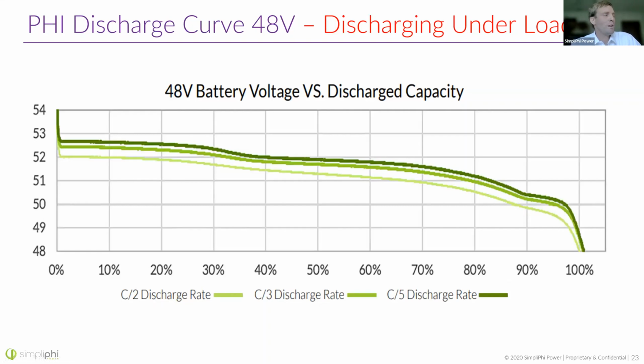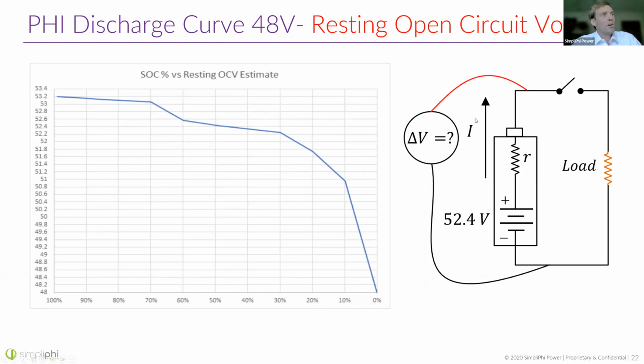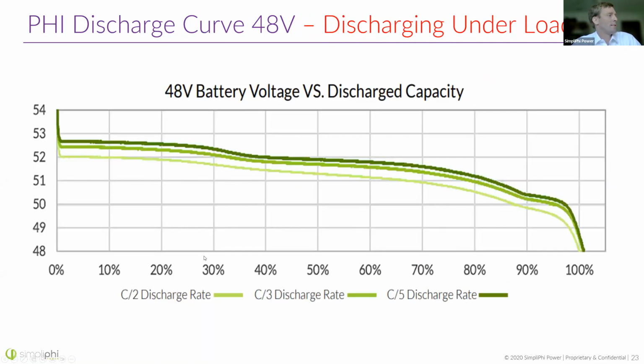So what I've shown you here is the state of charge voltage as a function of the discharge rate. Let me go back to the previous slide. As I vary the current out of the battery, a C/2 discharge rate is the lowest curve here, discharging our battery as fast as we can. For our 48-volt battery, that's 37.5 amps coming out. You can see that even at close to 100% state of charge, we're down at 52 volts if discharging with I being 37.5 amps.